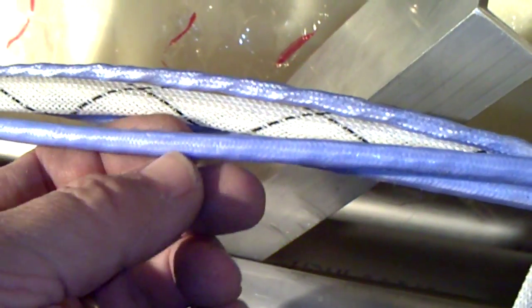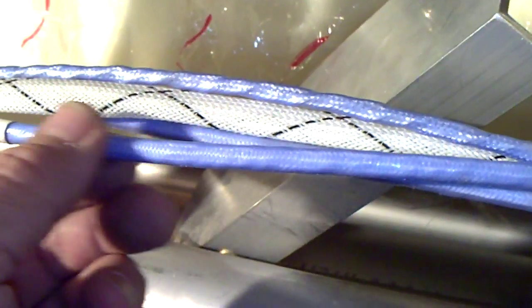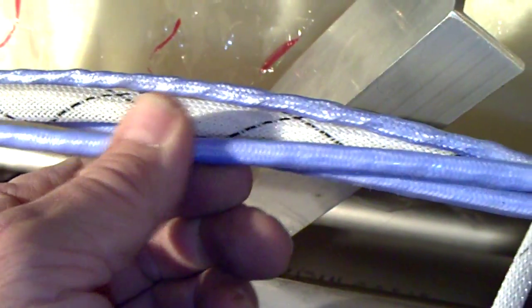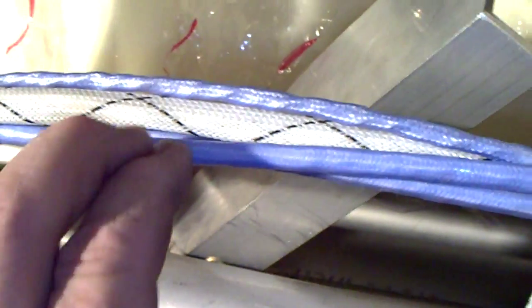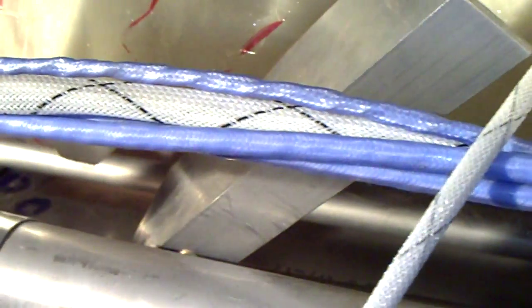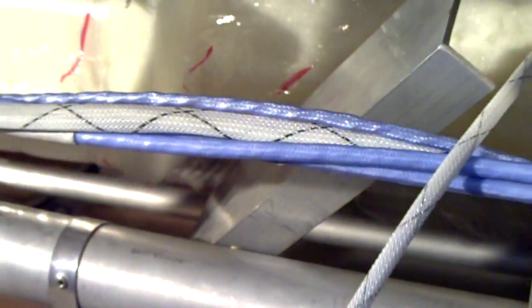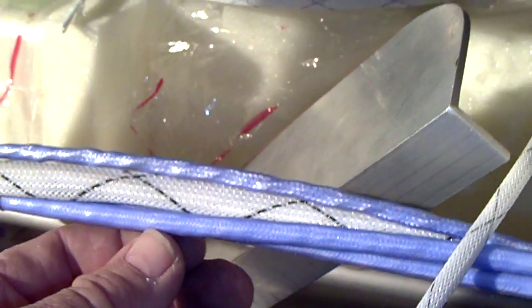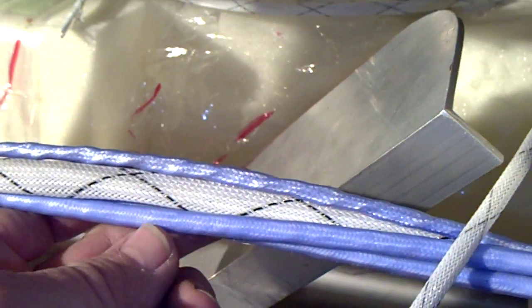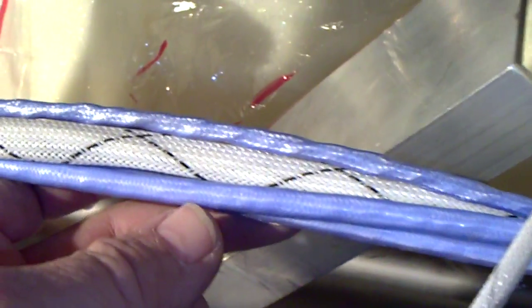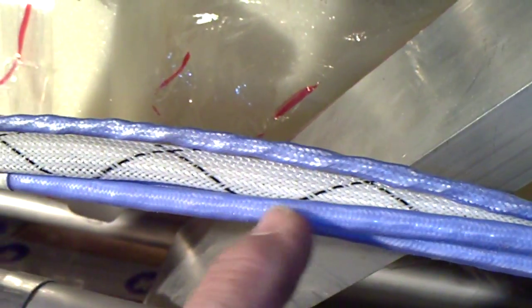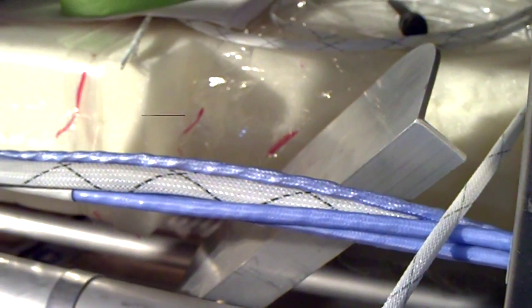And it also has an outer braid, a steel braid for grounding, to protect the signals from getting injected into this wire bundle. And that will eventually be grounded in the video covering the wiring techniques and crimping and terminating wires. These wires will cover how to make a splice, an environmental aircraft approved splice, along with how to run a solder ground on the braiding that's on the inside of this wire to ground signals from the engine into the airframe ground and prevent noise from getting into your circuits for your audio.